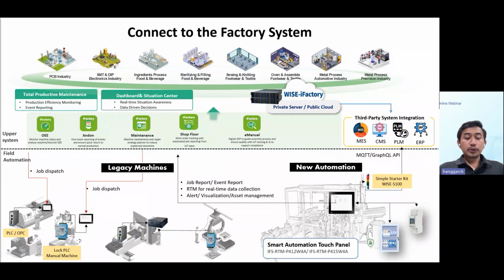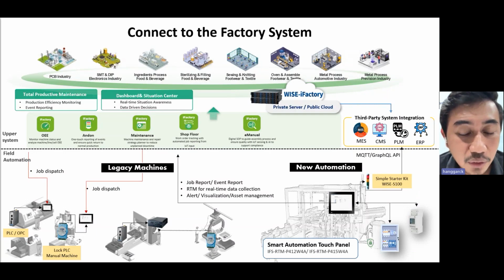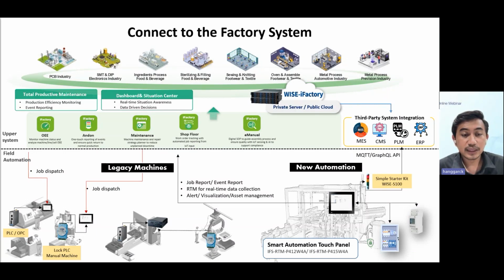Here is the topology of the implementation. Starting from the first implementation, if you have a PLC or OPC, we can use the IoT data gateway or RTM, as mentioned before, to pull the data, since this IoT gateway already supports more than 200 protocols of PLCs. Now, how about if you have a lock—mostly the issue from factories is that the machine is locked by the vendor and we cannot pull data from it. In this case, I suggest using remote IO, such as the Advantech data acquisition module (Adam), to pull data from the machine. You can tap from the relay or add a new sensor.